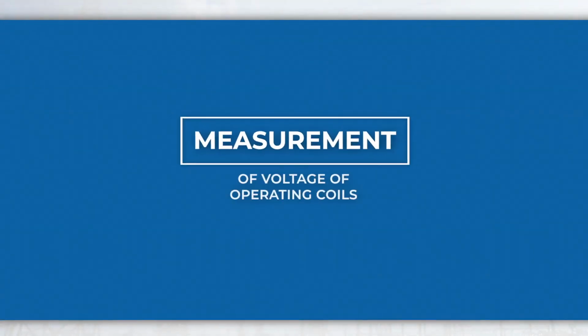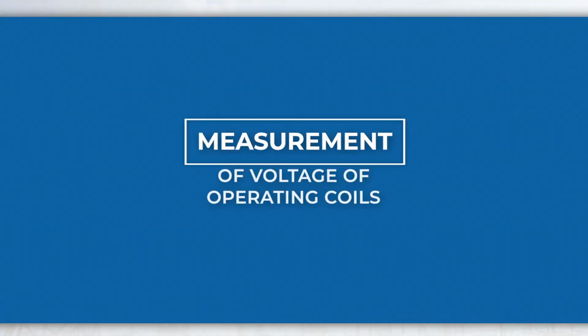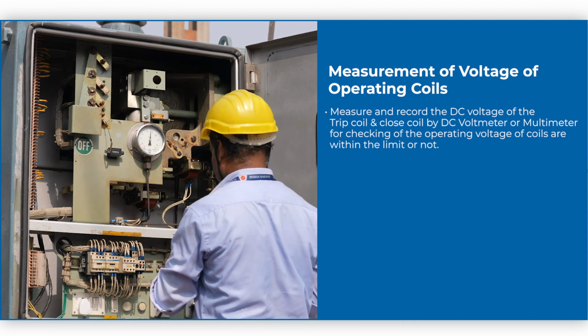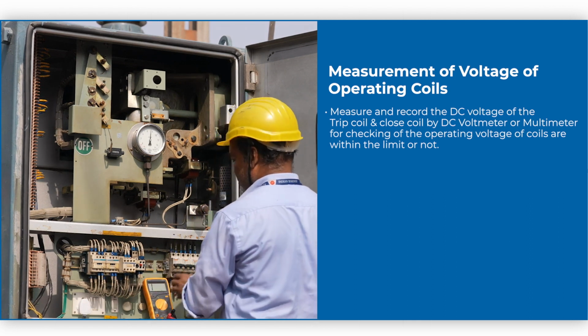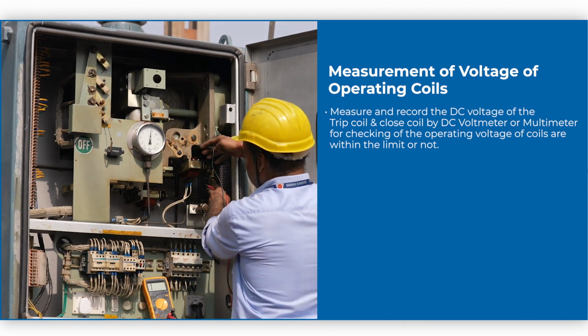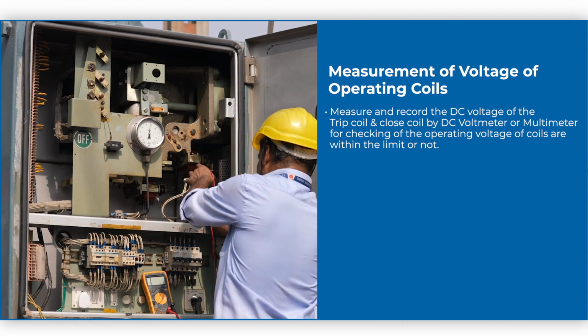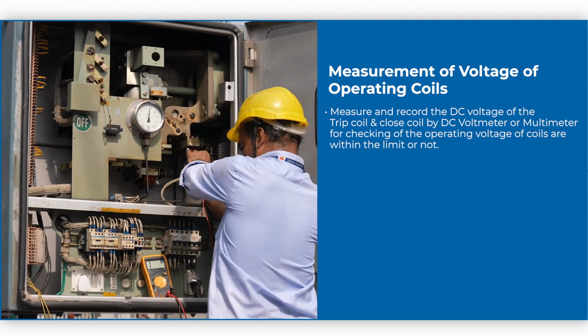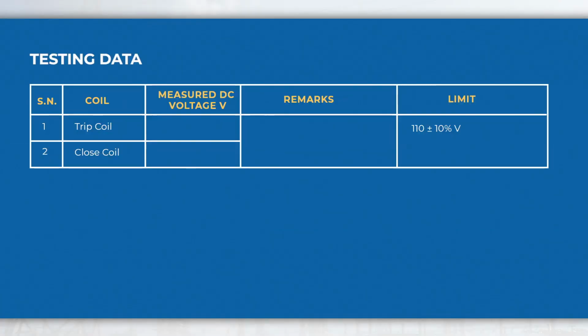Measurement of voltage of operating coils. Measure and record the DC voltage of the trip coil and close coil by DC voltmeter or multimeter for checking whether the operating voltage of the coils is within the limit or not. Testing data may be recorded in the format given below for evaluation and future reference.